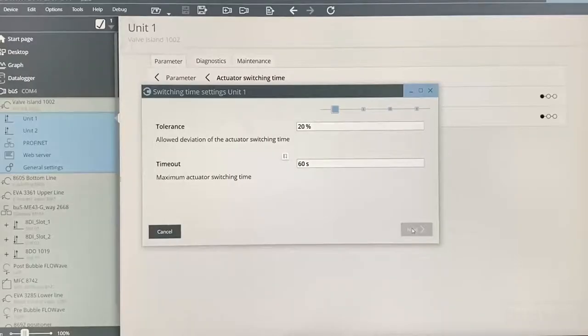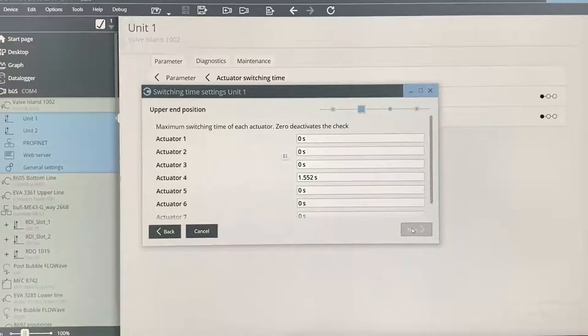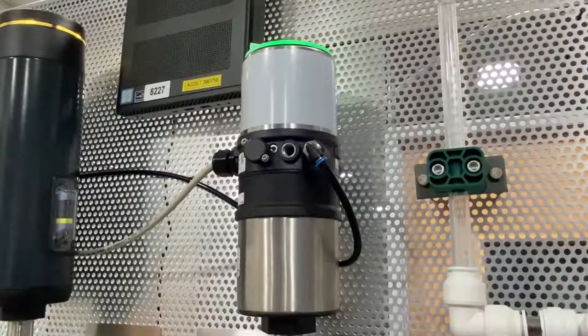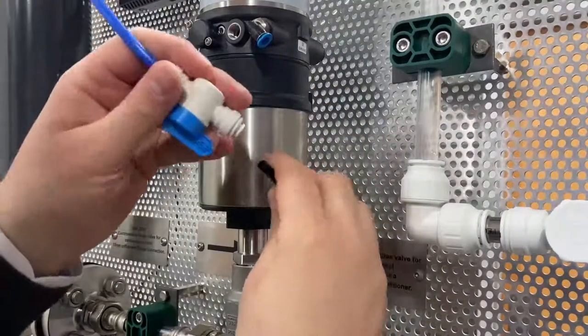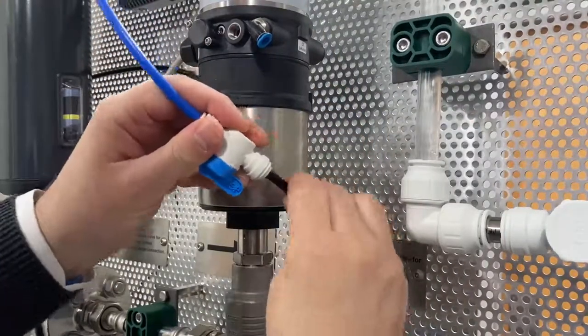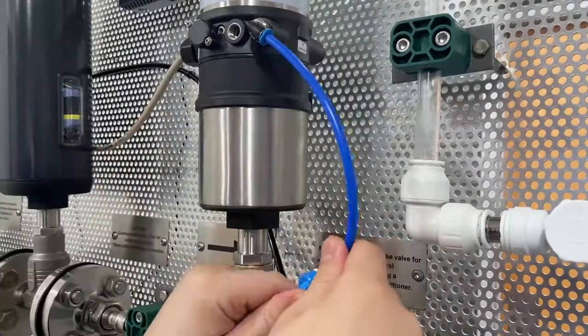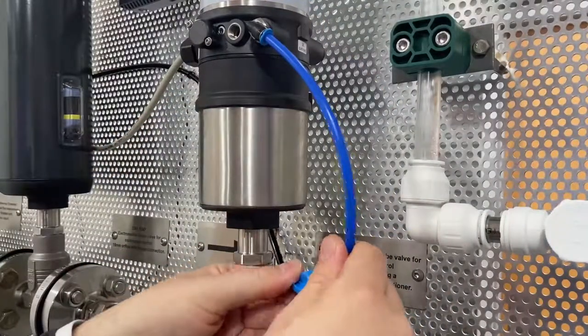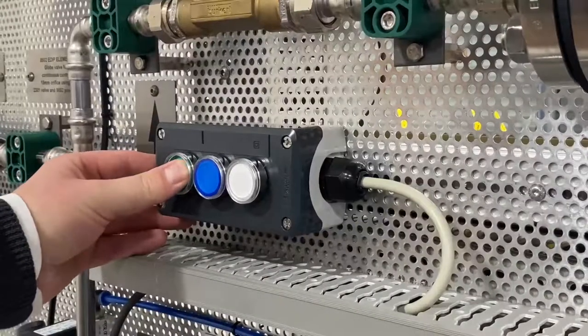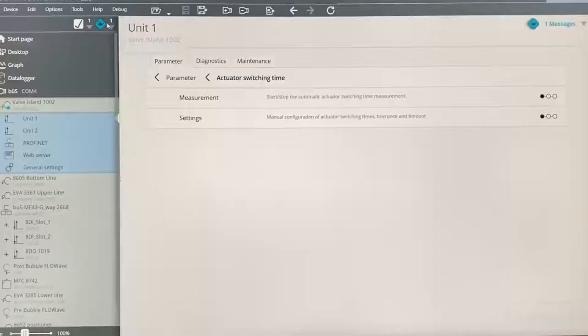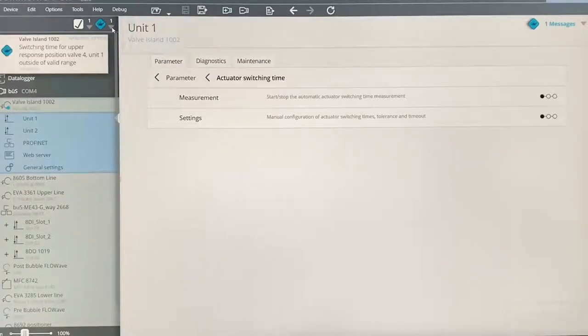Pressing next will take you to a review of the recorded switching times, which can be adjusted if necessary. Press next and finish as directed. Now we will actuate the valve to simulate normal activity. I will then restrict the process valve supply, which will slow the actuator down and will trigger a maintenance warning. You can now see a blue advisory notification on Communicator that says the switching time is now out of range.